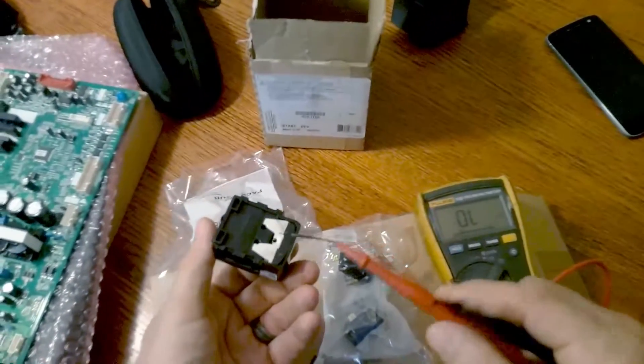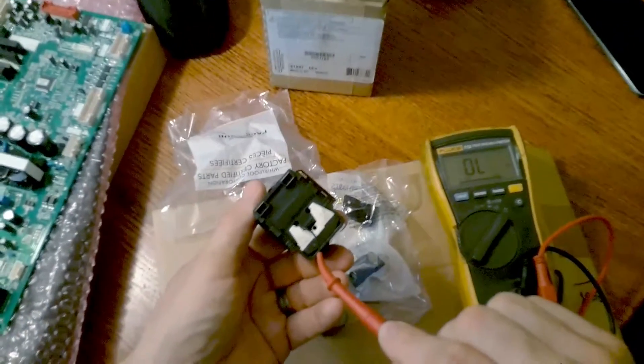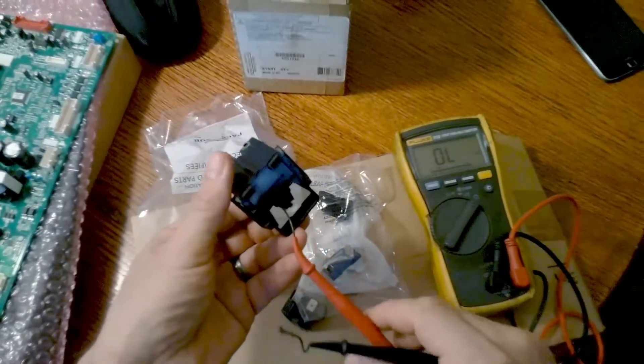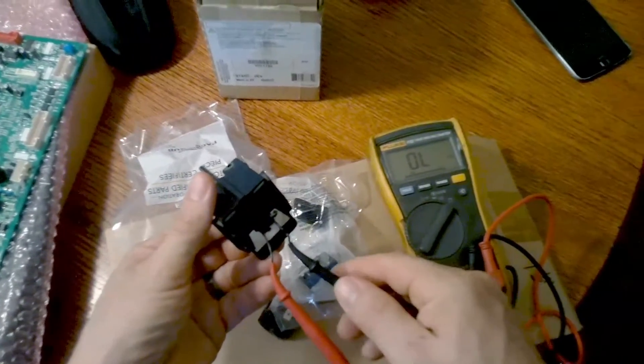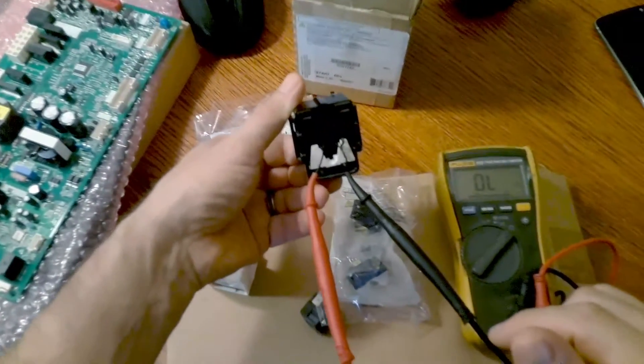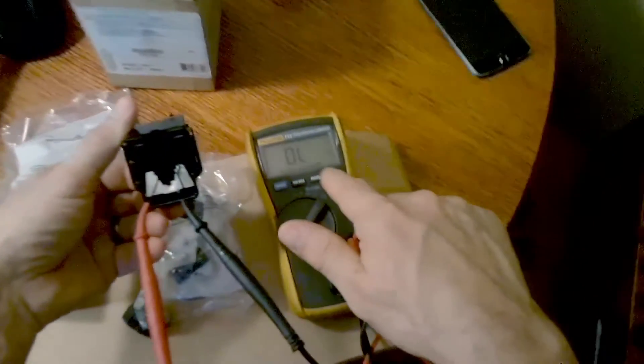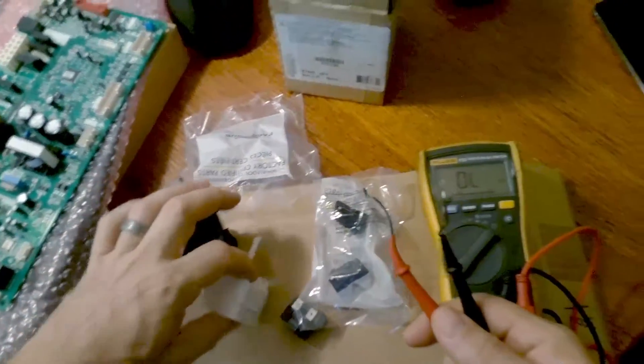So this is a bad relay. This is one I replaced, but this is a bad one so it's a great example. Place your red and your black prong in these two holes and you should read like 0.4. As you can see here, it's open line, so that's a bad relay.